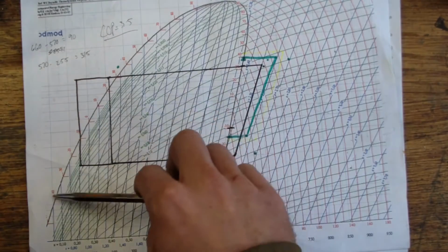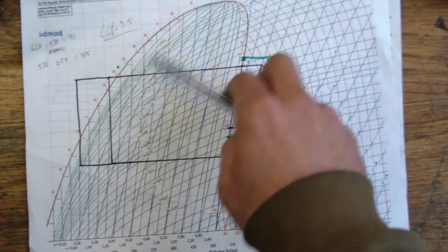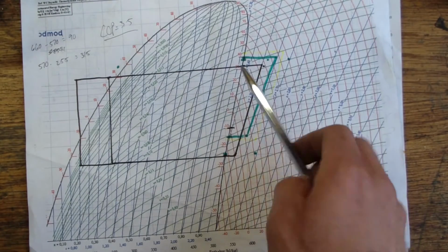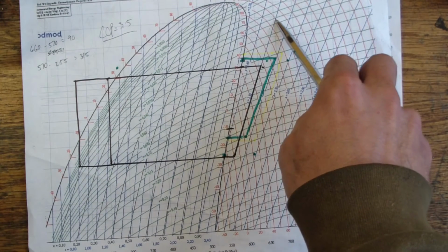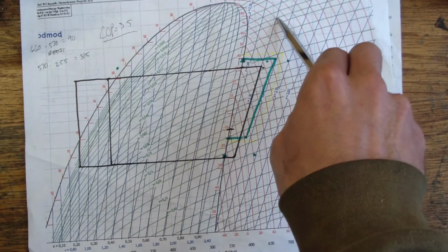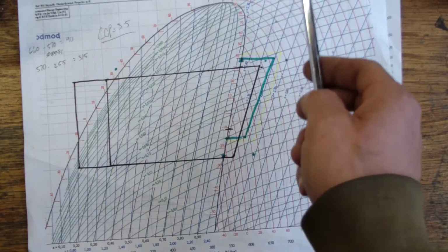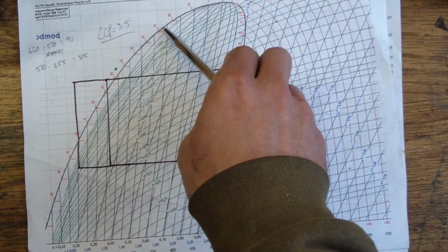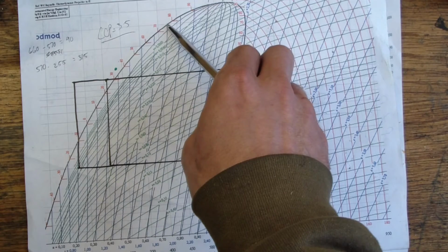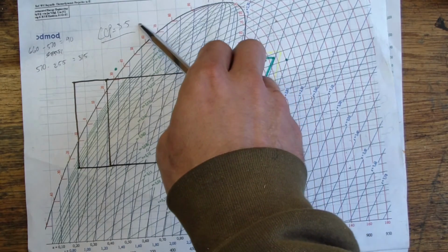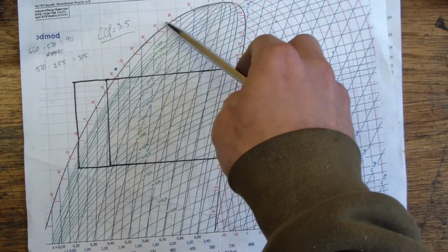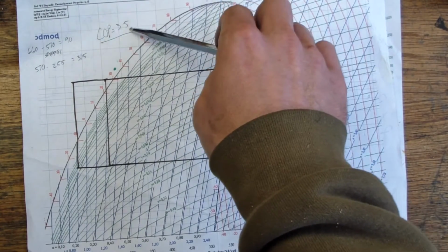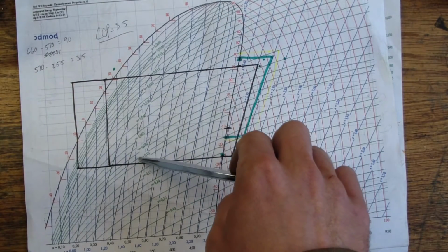The other thing is we can see the shape of the saturated vapor line on the saturated curve leans off to the right. So if our pressure increased significantly, and the discharge temperature and pressure were way up here, and we discharge at a constant pressure, assuming no pressure drop through the condenser and evaporator, just to keep it simple, we see that the saturated liquid curve is much further over to the right. To get much subcooling at all, because our head pressure is so high from a higher ambient temperature, we can't get far enough over to discharge a lot of that enthalpy and lower the refrigerant temperature. We're only going to end up somewhere in the middle once we finally exit the throttling device.